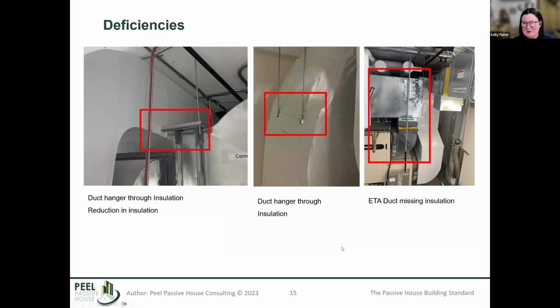And some wonderful more examples here. We had a project that was submitted for certification that was missing insulation entirely on a duct run to the outside. Some hangers were going through insulation, just really not that great, especially when they result in a reduction in the insulation. It can be really terrible for the performance of the system.